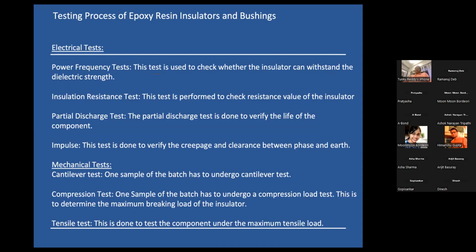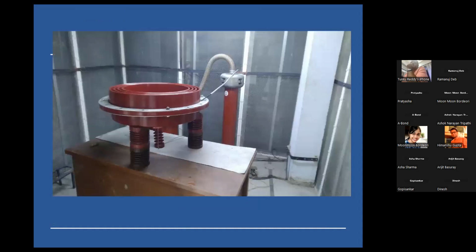Now, after the electrical tests are completed, we have to undergo the mechanical tests. Cantilever tests, compression tests, and tensile tests are done. The compression test is done to check the maximum breaking load of the insulator. The tensile test is done to check the maximum tensile load. This is a picture of a testing apparatus. This is a power frequency test.